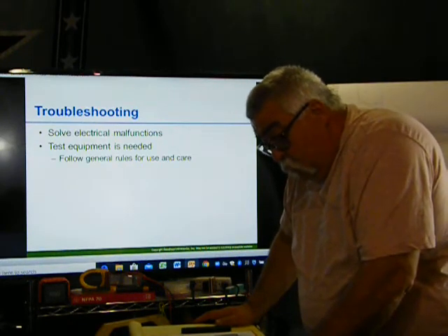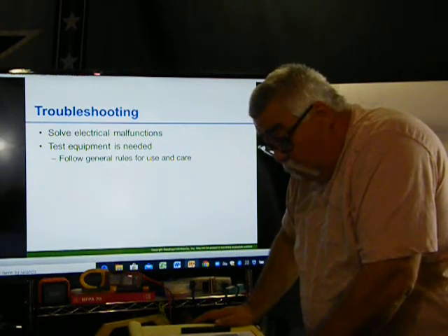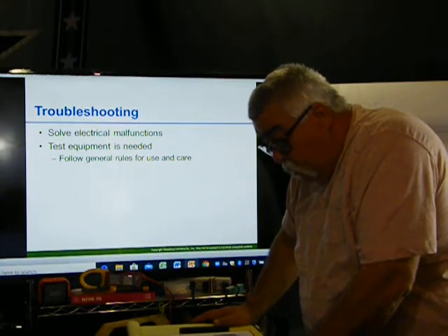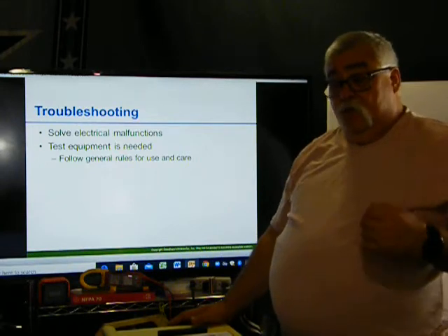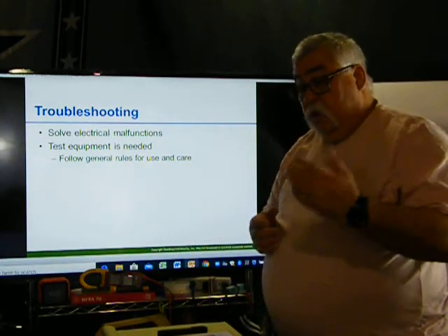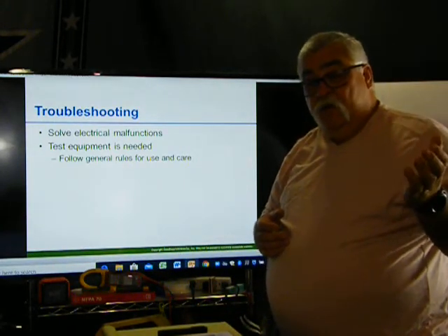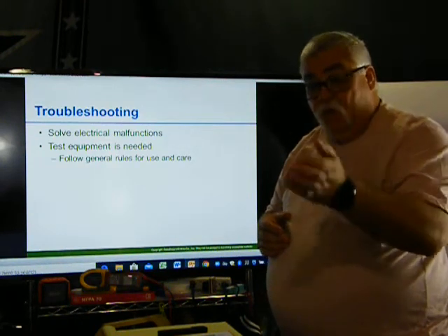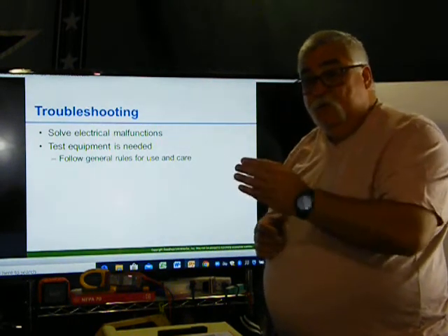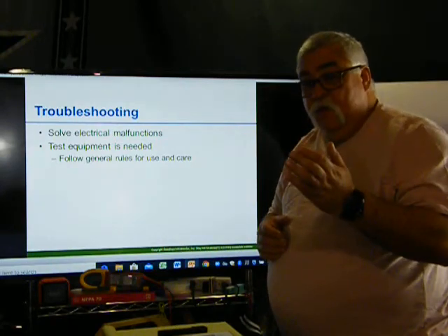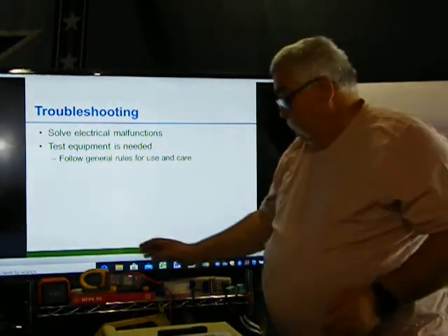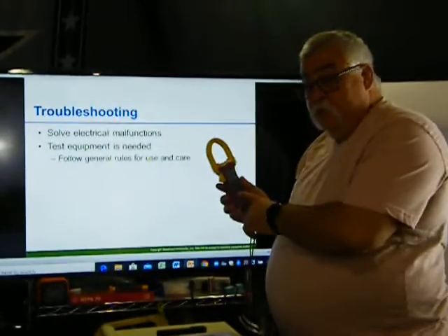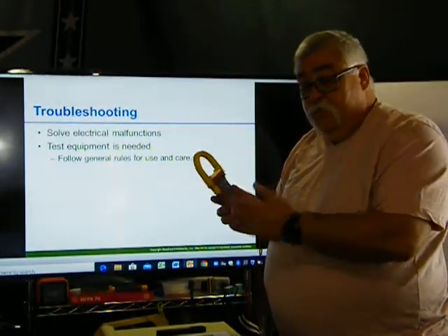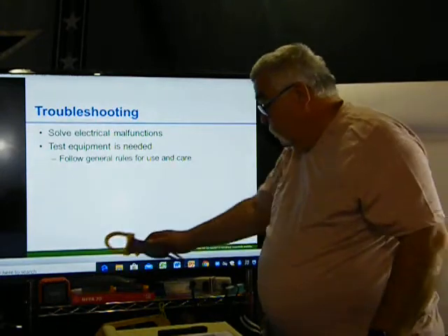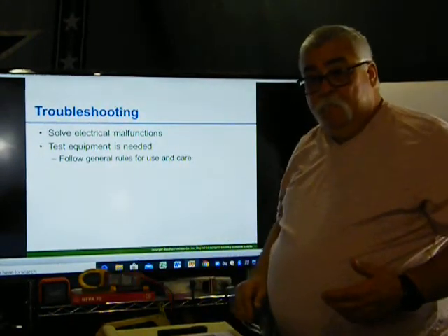When using an instrument with several scales, always test with the highest scale to prevent overloading. Okay, so if you have a multimeter and the multimeter has, say, 250, 480, and then a 600 or 700 or whatever it may be, go to the highest rating. It's still going to read it, especially if it's a digital. It's still going to read the voltage. It doesn't matter. It's going to give you a voltage reading, so it's not going to hurt anything.